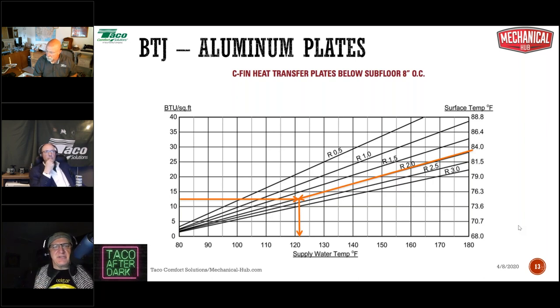The first stipulation, and all three have to be met in order to put these together, is that the usage pattern of all three of the rooms has to be consistent. They have to be considered like the same big area. So we're talking kitchen, breakfast room, family room that are kind of open to one another. That's a candidate for zoning a bunch of rooms together. Kitchen, breakfast room, bedroom, no, not at all.